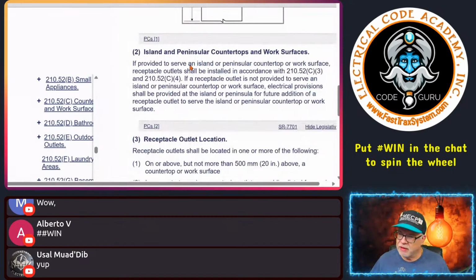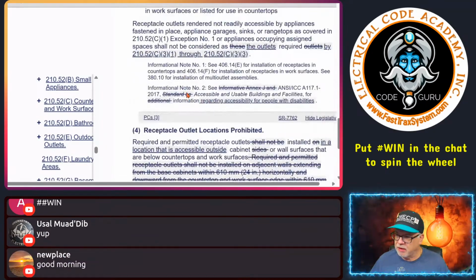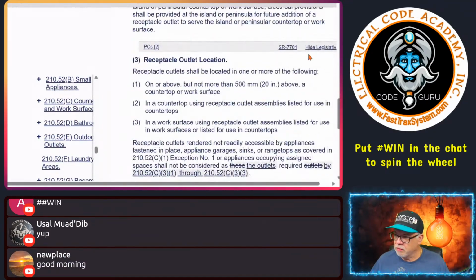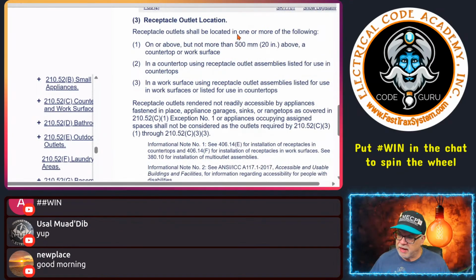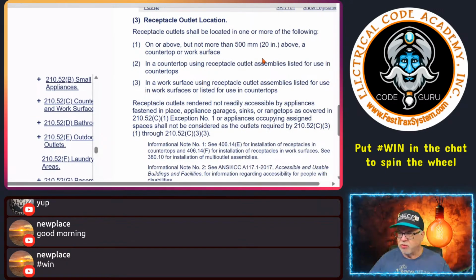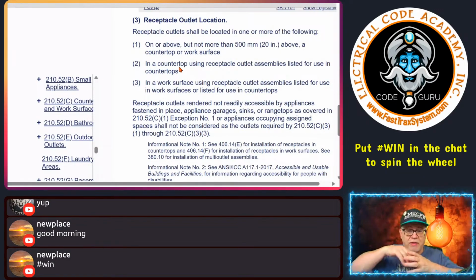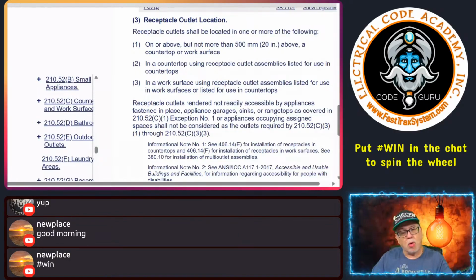Okay, so here we are: islands and peninsular countertop work surfaces. So here's where you're coming down, and let's hide the legislation so we can just see the code language. Receptacle outlets shall be located in one or more of the following locations: on or above, but not more than 20 inches above a countertop or work surface, or in a countertop using receptacle outlet assemblies listed for use in countertops. Those are the kind that go into the countertop and either flip up or pop up. They are not the ones with the cord and plug cap on the end that plug into a receptacle under the counter. These are hardwired, by the way, and they are listed assemblies for this application, okay?